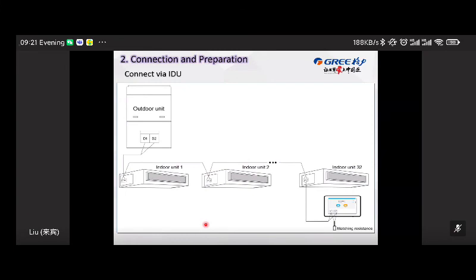Okay. And for the connection, you can connect the central controller to the indoor unit side, to the last indoor unit, and connect with the matching resistor. This resistor is very important. A lot of communication errors and display errors where the indoor units cannot be found are caused by the matching resistor. So do not forget this resistor when you connect the central controller to the last indoor unit. Okay, that's the first method.